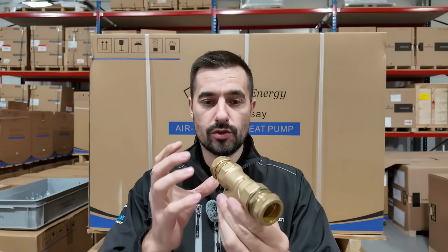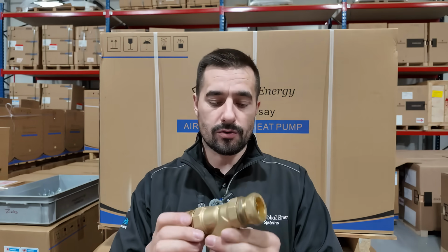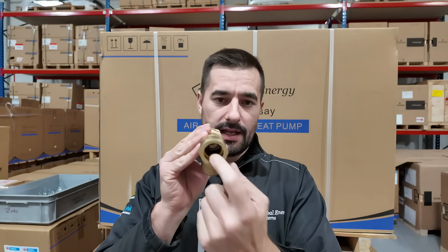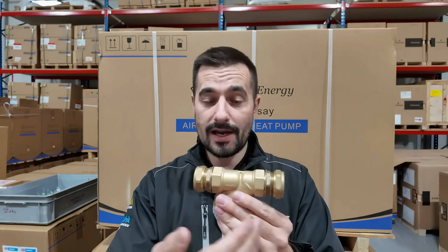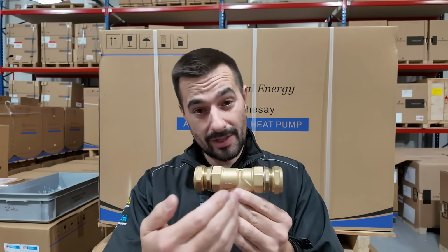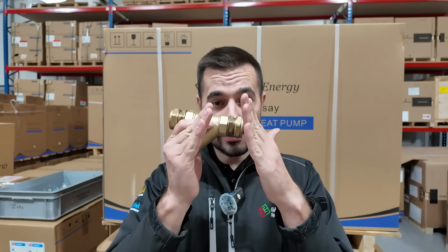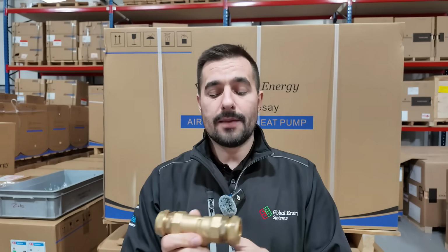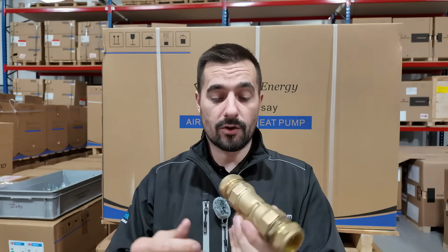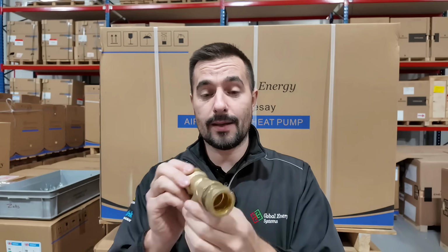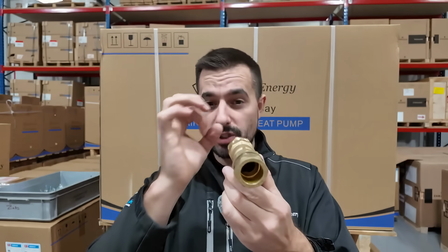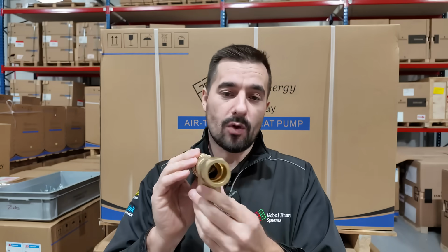Now, Y strainers do the job in that they protect the condenser. However, they also cause their own problems. They've got quite a narrow waterway, so they've got a very low kV value, which means that as you pass more water through them, the pressure builds backwards up. It's almost like a 3-lane motorway going into one, so the pressure builds. It makes it very difficult for the pump to overcome that pressure. And then the other thing is, as debris does get captured within it, because it's a small gauze and a small cross-sectional area, they block up quite easily.